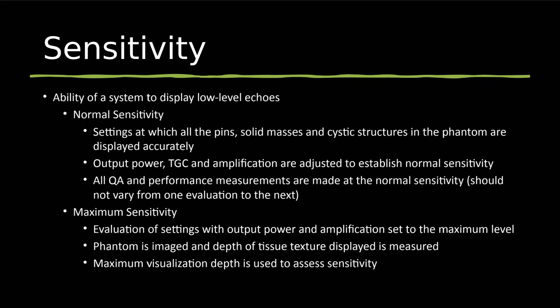So sensitivity, we just said, is a performance measurement that we are looking for. So basically what we do with this is we're looking to see what the system's ability is to display low-level echoes. So we kind of want to test the normal sensitivity of our system and the maximum sensitivity. So normal sensitivity, we're keeping all of our settings on an average basis. So when you look at your TGC, it's kind of like in the middle of the bars. Your gain setting is set at a medium gray.